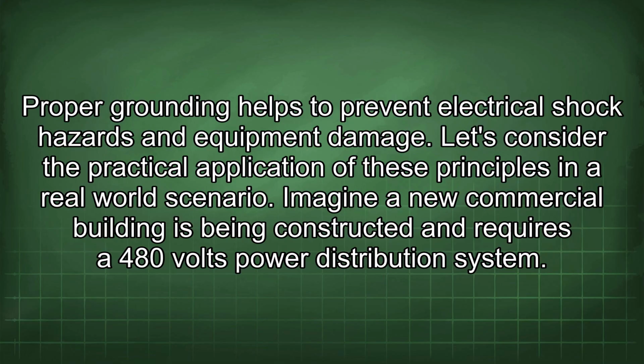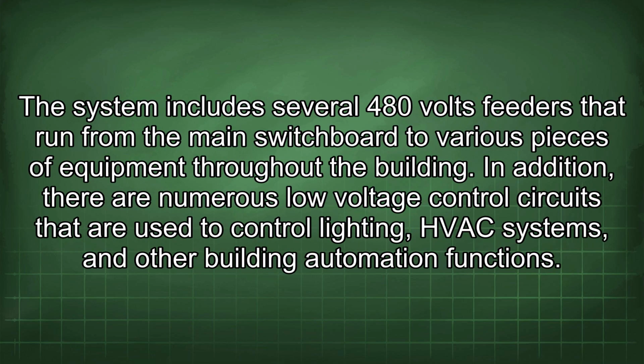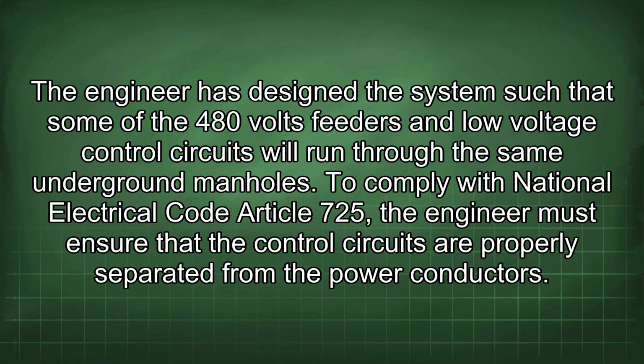Imagine a new commercial building is being constructed and requires a 480 volts power distribution system. The system includes several 480 volts feeders that run from the main switchboard to various pieces of equipment throughout the building. In addition, there are numerous low-voltage control circuits that are used to control lighting, HVAC systems, and other building automation functions. The engineer has designed the system such that some of the 480 volts feeders and low-voltage control circuits will run through the same underground manholes.